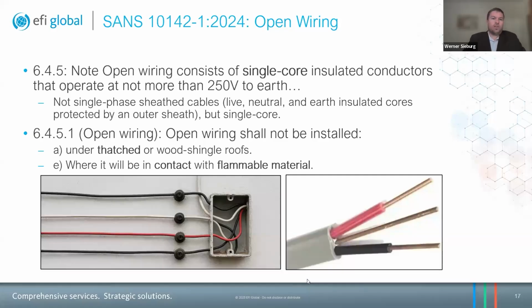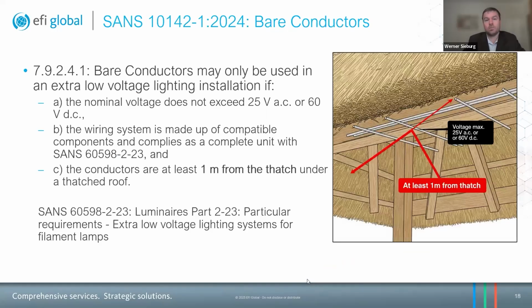So 6.4.5.1, this above, we're just in the definition. Open wiring shall not be installed under thatched or wood shingle roofs. This is quite important, obviously, in a thatch environment. And also where it will be in contact with flammable material. I think this is quite straightforward. I just thought I'd put it out there. In instances where there's a bit of an older wiring system, we might need to consider that.